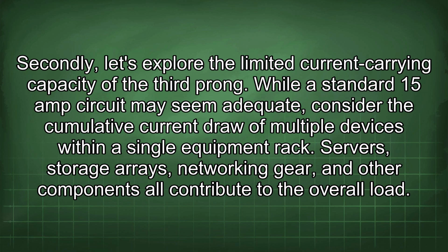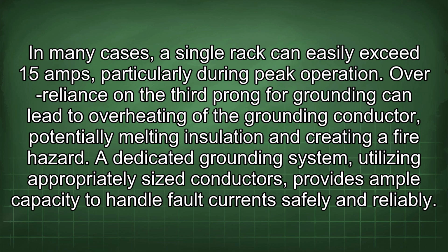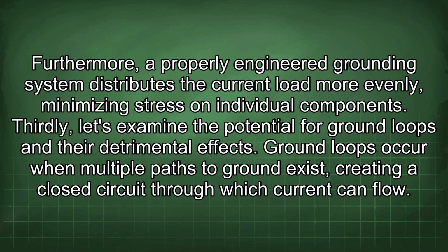While a standard 15 amp circuit may seem adequate, consider the cumulative current draw of multiple devices within a single equipment rack. Servers, storage arrays, networking gear, and other components all contribute to the overall load. In many cases, a single rack can easily exceed 15 amps, particularly during peak operation. Over-reliance on the third prong for grounding can lead to overheating of the grounding conductor, potentially melting insulation and creating a fire hazard. A dedicated grounding system, utilizing appropriately sized conductors, provides ample capacity to handle fault currents safely and reliably. Furthermore, a properly engineered grounding system distributes the current load more evenly, minimizing stress on individual components.